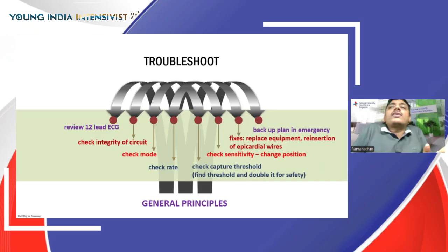Essentially, I'll talk about it, but before that, let me cover how you deal with failure to pace. Failure to pace, essentially, you identify when your pacemaker spike should appear, but it doesn't. So there is no electrical output from the pacing wire tip. It's usually a lead malfunction or an unstable connection. Sometimes it can be due to electrolyte disturbances. Clearly, you need to check the power. The usual bedside maneuver we all do is increase the output and see whether it works. We may even change it to an asynchronous mode to make sure that there are no other complicated things that are troubling this pacemaker.